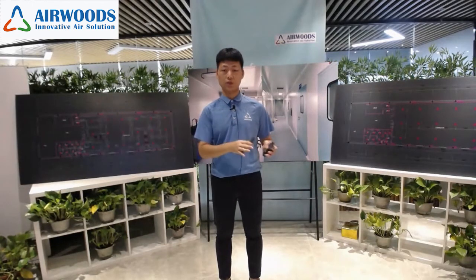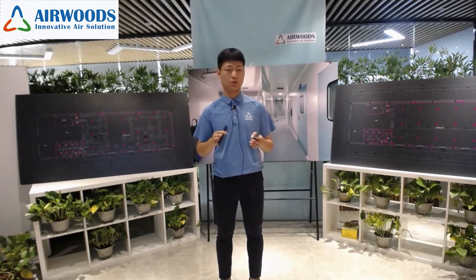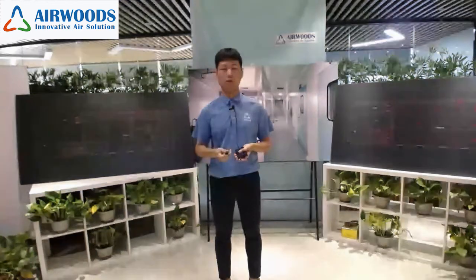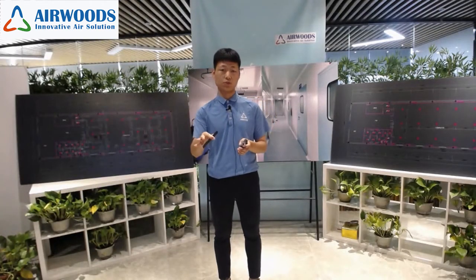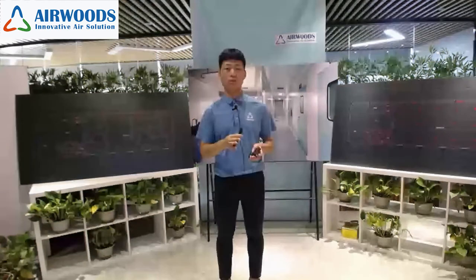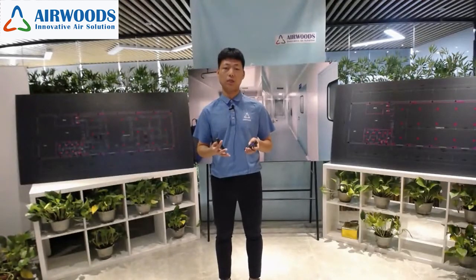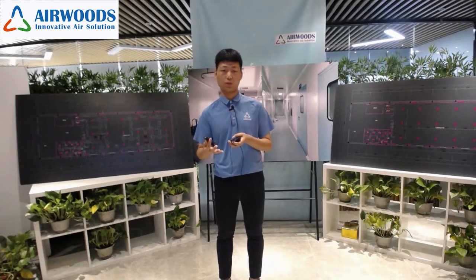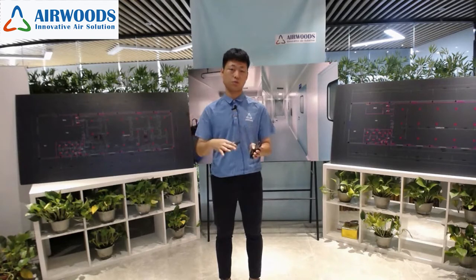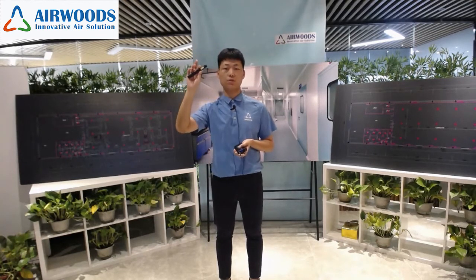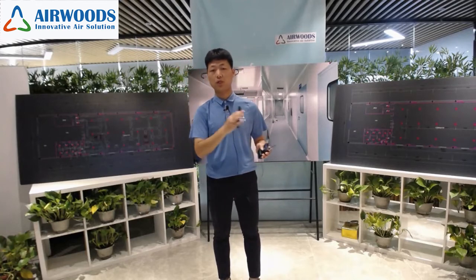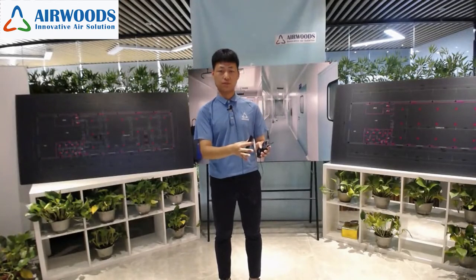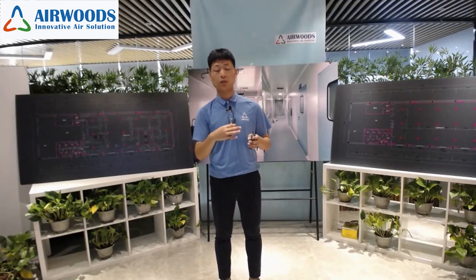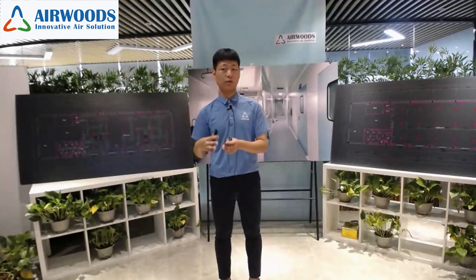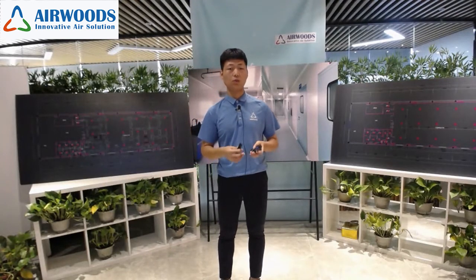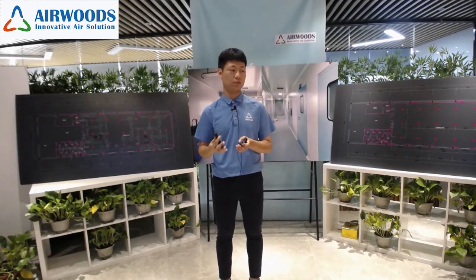Actually, we need to calculate the airflow based on the air change rate and the cleanliness standard. Usually for the main production workshop, it is the ISO 8 standard, right? So the air change rate is normally 18 to 20 times per hour. So we calculate the total supply air of these rooms. And for the diffusers at the terminals, there are manual dampers to regulate the supply airflow to the rooms. We can also monitor the room pressure to know if the airflow meets our design standards. So we have many ways to manage the airflow of each room.